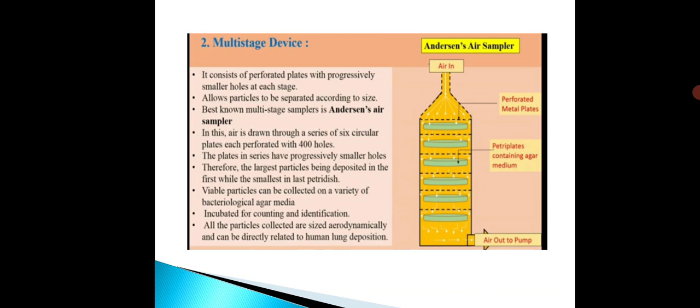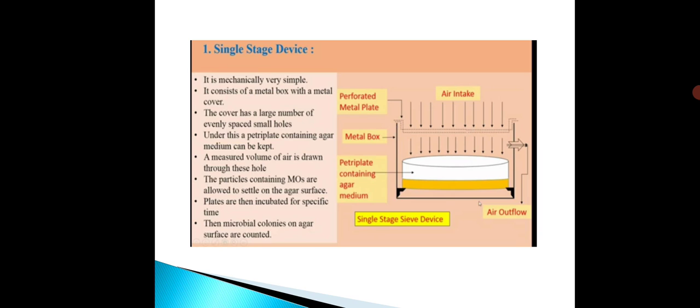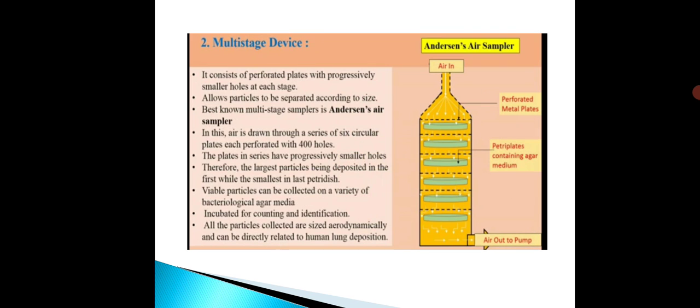To summarize, today we studied the first method — impaction on solid — with two device types: single-stage device with just one petri plate where air is allowed in and microorganisms settle for incubation; and multi-stage device (Anderson's air sampler) with six petri plates and six perforated metal plates of different pore sizes. Larger particles settle on the first agar plate and small-size microorganisms settle on the last plate because the final perforated plate has fine pores. In the next lecture we will discuss our next method. Thank you.